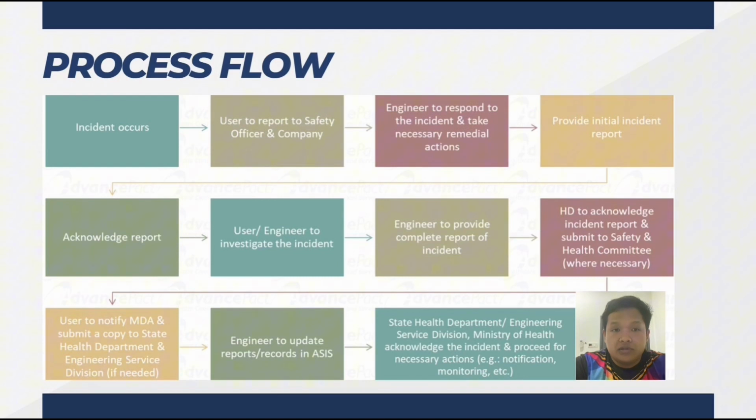The engineer will acknowledge the report and investigate the incident. The engineer will provide a complete report of the incident and then deliver it to the head of department to acknowledge the incident report and submit to the safety and health committee. Then the user will notify the Medical Device Authority and submit a copy to the state health department and engineering services division. Then the engineer will need to update reports or records in ASIS.